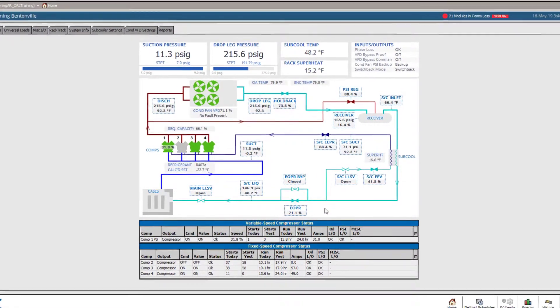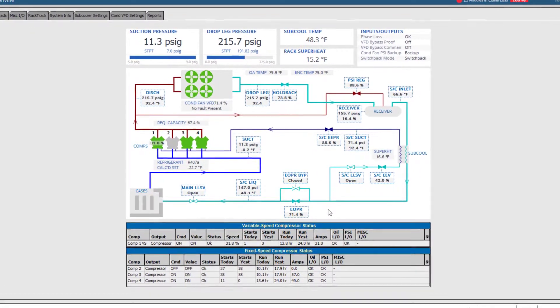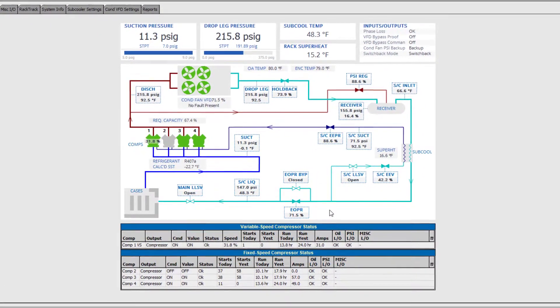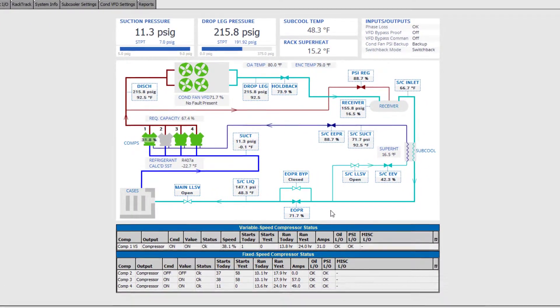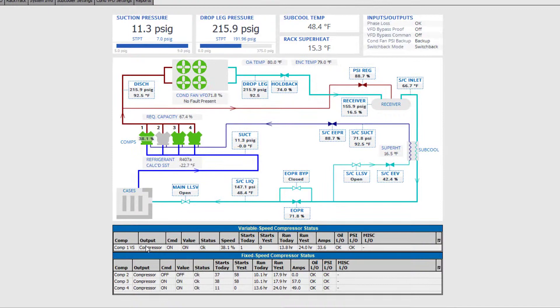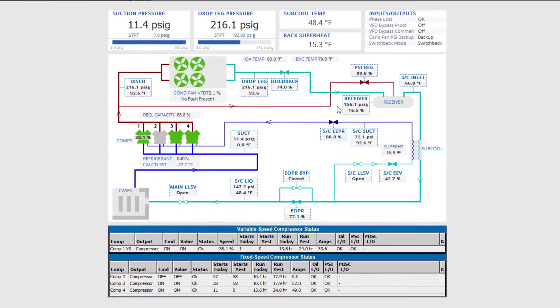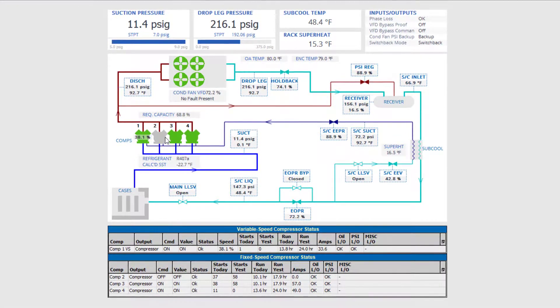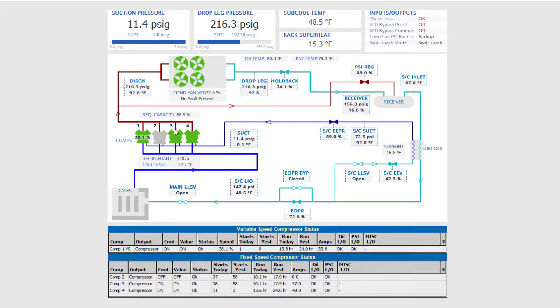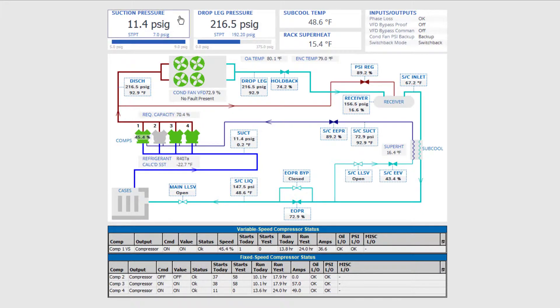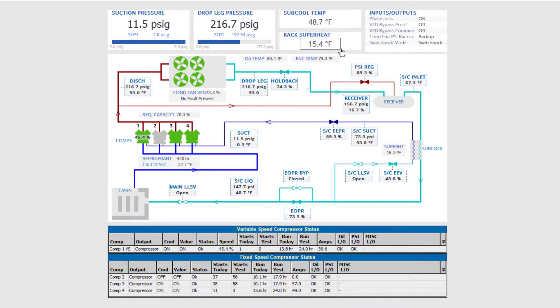There are often multiple places where you can force a point into override from the tabular fields as well as from the graphical interfaces. It is important to understand that overriding input points may affect multiple output points with unintended consequences.